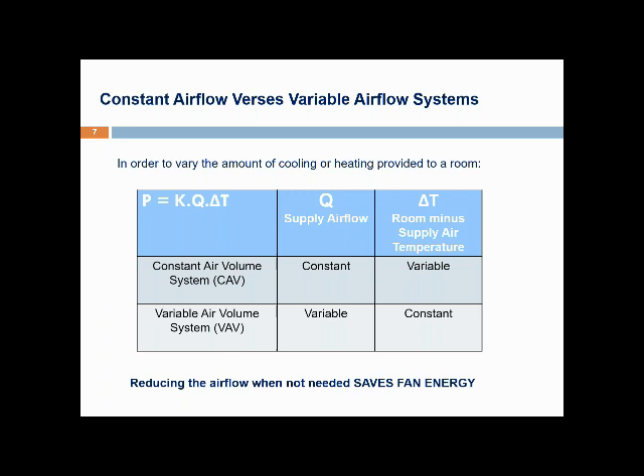The constant air volume system keeps the supply airflow constant and varies the delta T — the difference between room and supply air temperature — by varying the supply air temperature. The variable air volume system works in the opposite way: it varies the supply air volume while keeping the delta T constant by maintaining a constant supply air temperature. This results in the big benefit of VAV systems — by varying and reducing the airflow when not needed, we use much less central air handling unit fan energy, giving significant energy savings.